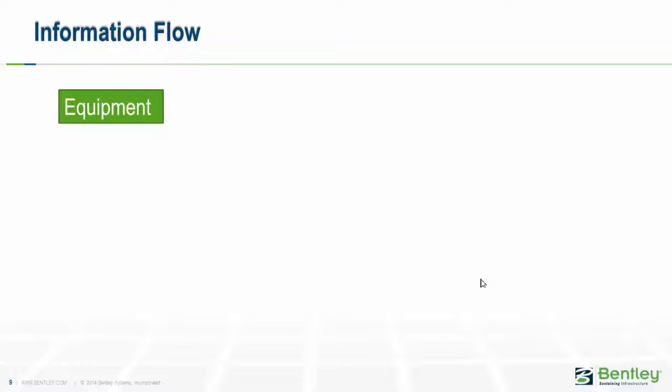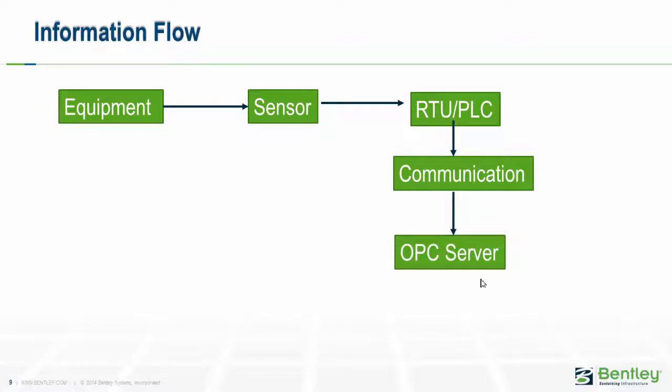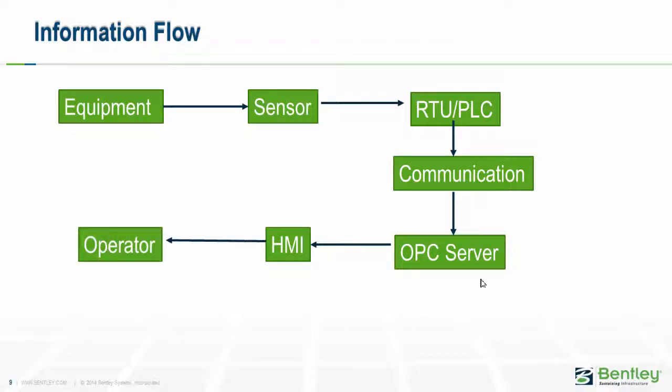Nowadays with SCADA systems we have this kind of information flow. There's some kind of sensor out in the system telling us what's going on in equipment, whether it's a tank water level or pump flow rate. That usually gets converted from an analog signal, usually a 4-20 milliamp signal, into digital signal that goes into a PLC or remote telemetry unit that gathers the data at the site. Then it goes through some communication system, whether radio waves, satellite, cell phones, or hard wire, to get data back to some kind of server in the control room. These servers use OPC as the standard for handling data. From there it goes into the HMI, the human machine interface, where the operator views what's going on.